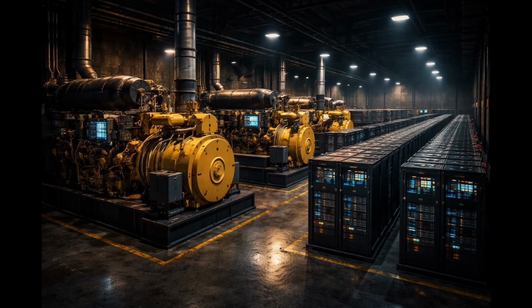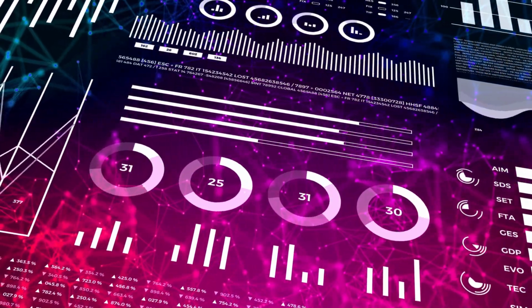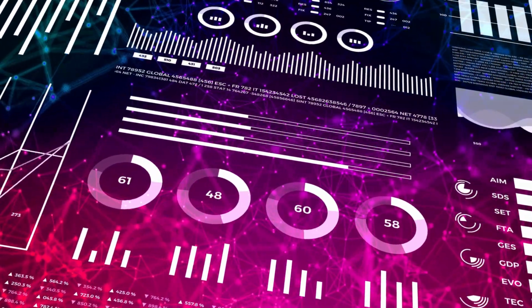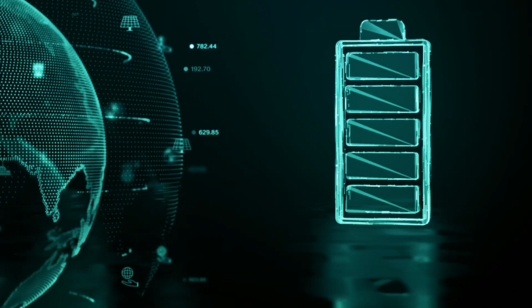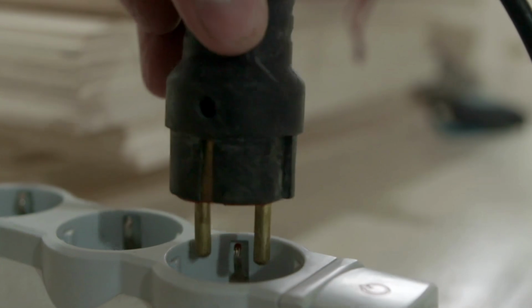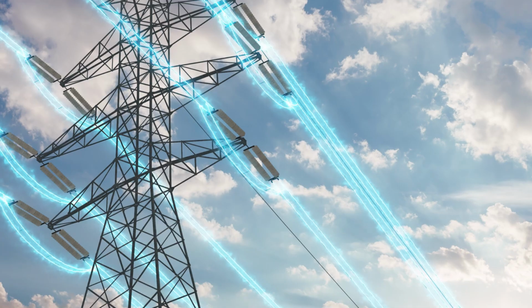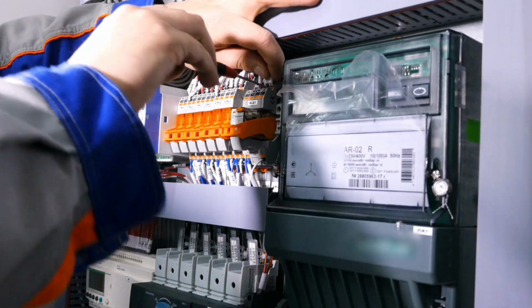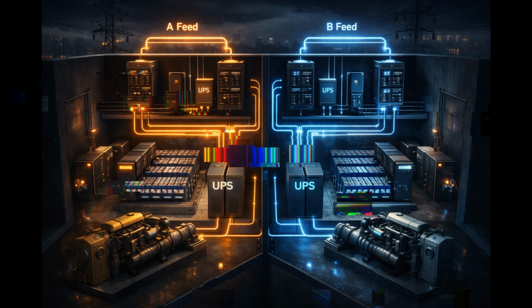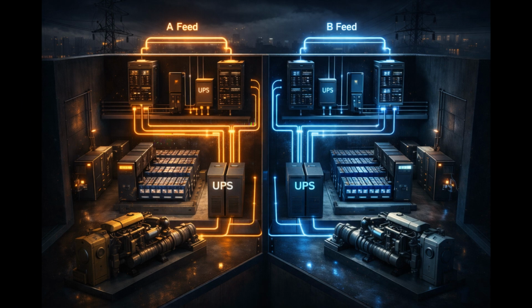At the lowest level, a data center is not about data. It's about power and heat management. Servers are useless without electricity, so everything starts with power intake. Data centers pull electricity directly from high-voltage grids, step it down using transformers, and then route it through redundant power paths. This redundancy is not optional. Every critical system follows an N+1 or even 2N design, meaning there is always backup capacity ready to take over instantly.